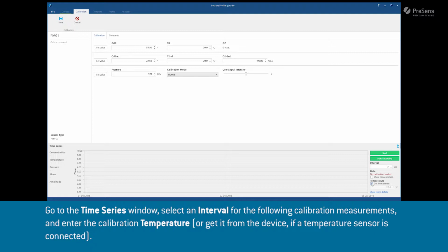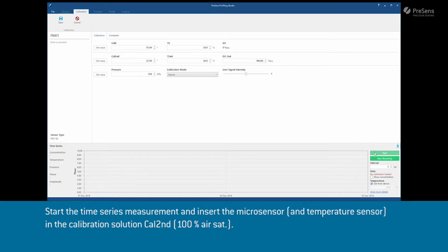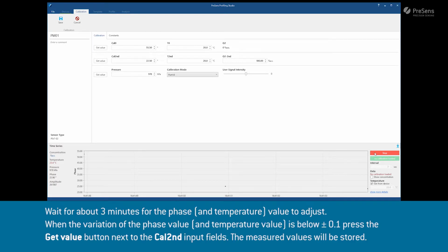Start the time series measurement and insert the microsensor and temperature sensor in the calibration solution called Cal second. Wait for about 3 minutes for the phase and temperature value to adjust. When the variation of phase and temperature value is below 0.1, press the Get Value button next to the Cal second input field. The measured values will be stored.